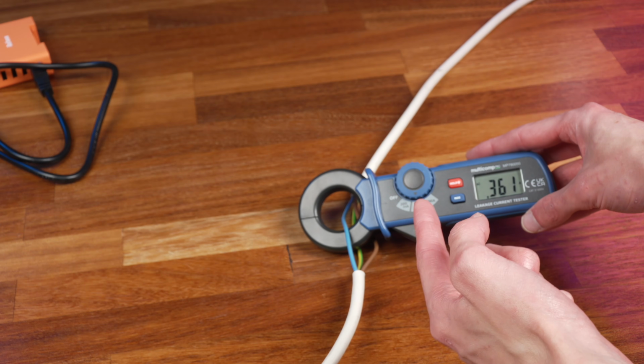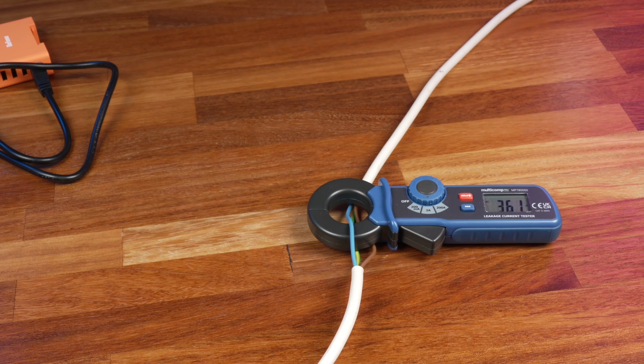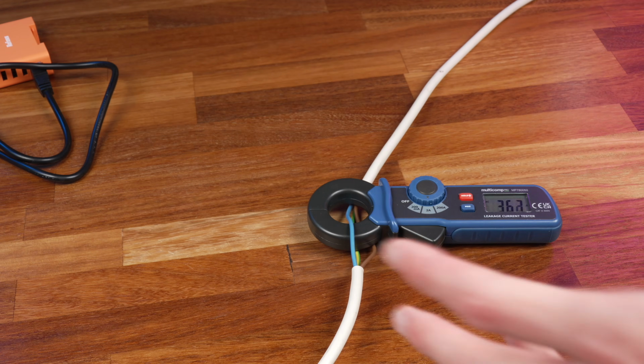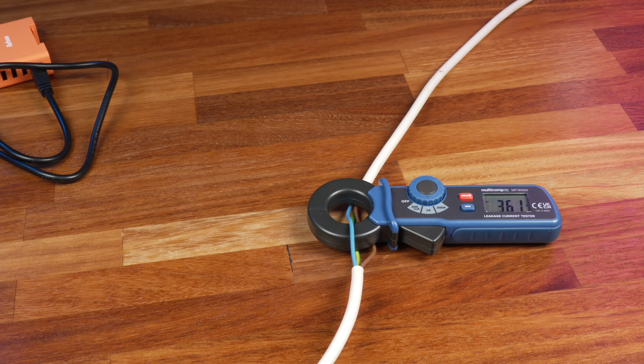And this is just something that's very handy to keep in mind, since when you're installing the CTs, you may come across situations where it's easier to install it around the neutral wire instead of the line wire. There might just be a bit more slack on the neutral, or your neutral wire may be connecting to a terminal bar somewhere in your consumer unit where there's a bit more space around it. And for my setup here, there's definitely a couple of circuits that I'm probably going to do that with, so stay tuned to see that later in the video.